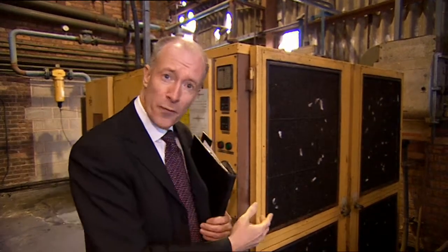Fresh air is continuously taken into your compressor to create the compressed air. It's important to keep your filters clean. Dust and debris building up on the filter just causes a pressure drop. This can cause a 2% loss in efficiency. Change your filters regularly.